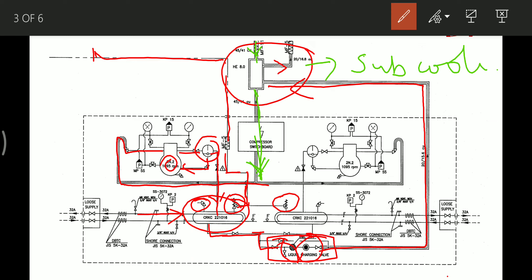This filter and dryer unit also has a liquid charging connection. Also on the compressor, there is a lube oil charging cock. There are pressure switches for operation of the compressor — a high pressure cutout and a low pressure switch — and a lube oil pressure switch that provides a trip in case of low lube oil pressure. There is also a differential gauge on the suction side showing suction pressure and lube oil pressure, and a discharge gauge on the discharge side.